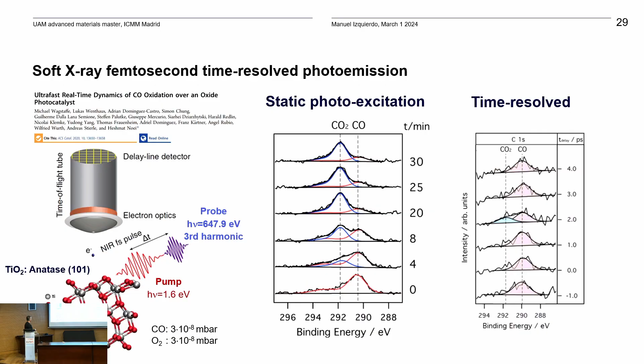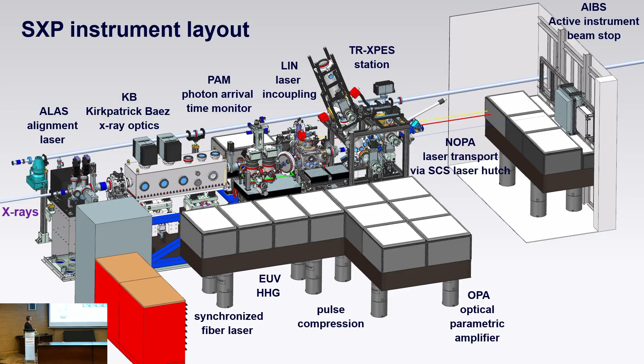That's a very interesting question. Thank you so much. In principle, the catch is that you have a wide acceptance angle. So, and if I go, maybe, no, I need to go back. Okay, if I go, no, it has to be forward. So this is the idea. Basically, you can collect all photoelectrons in a cone of 40 degrees, because what you do is you put a very high voltage at the first element after the sample, and basically all the electrons will be collected.